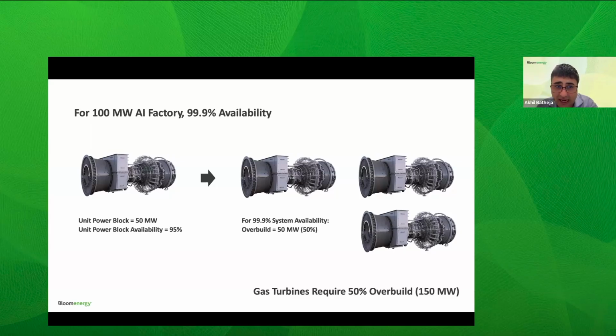To hit that 3 nines, a couple of factors go into the math: the block size of the unit being built, and how available it is. Take a large open cycle gas turbine, say 50 megawatts, with about 95% availability. Because of that 5% unavailability, you have to build a third unit to hit 99.9% availability for your 100 megawatt load. That's about a 50% overbuild.